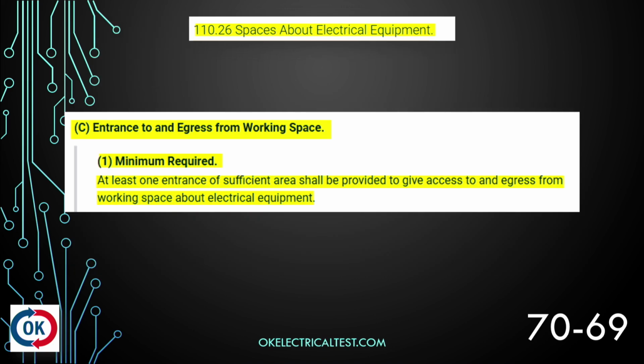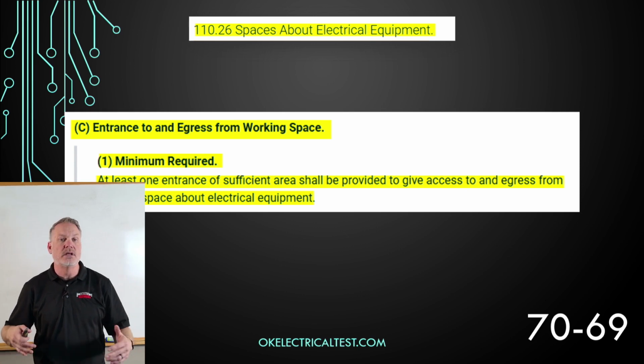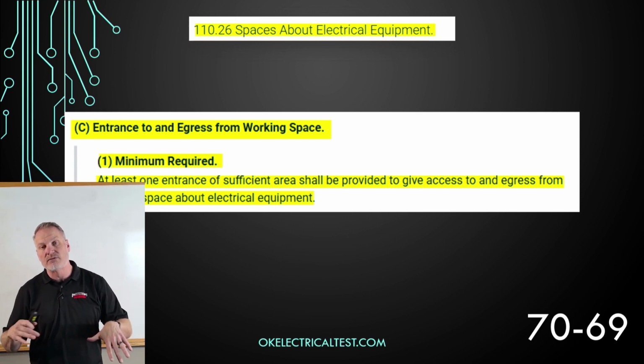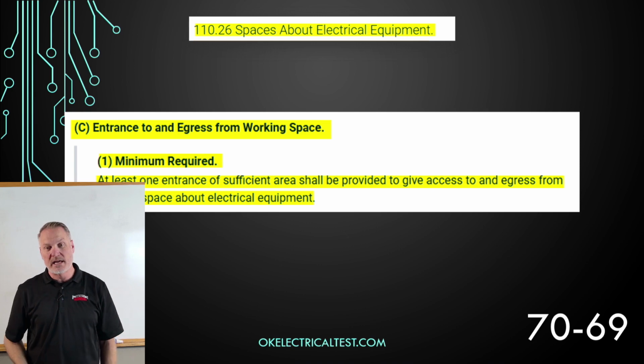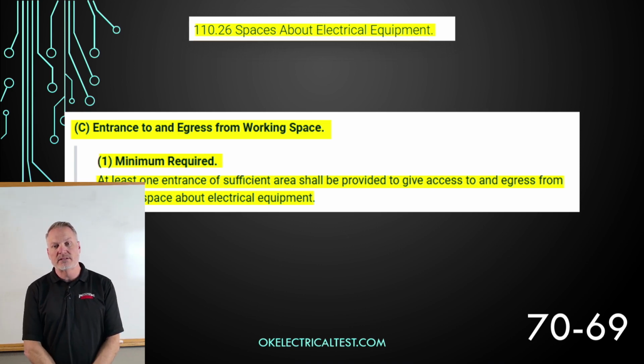Let's go still under 110.26, spaces about electrical equipment. We've got a letter C, entrance to and egress from the working space. And number 1 down below there, minimum required. It says at least one entrance of sufficient area shall be provided to give access to and egress from the working space about electrical equipment. Without any qualifications as to the size of the equipment, we do know that if the voltage is 1,000 volts or less, I need to have at least one way to get in and out, right? Access to and egress from.